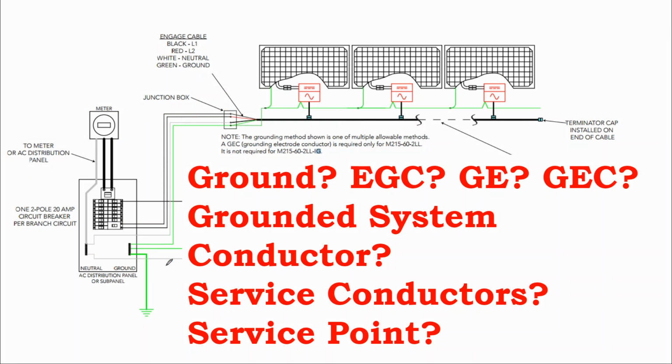There's this other part of the ground system, which I've been calling the drain. The effective ground fault path is the equipment ground conductor. This green ground fault path is sized for this equipment, for this circuit, going back to the service panel. And then based on the total size of the service, the drain is sized and makes that connection to ground. So we've got the equipment ground conductor that then feeds the grounding electrode.